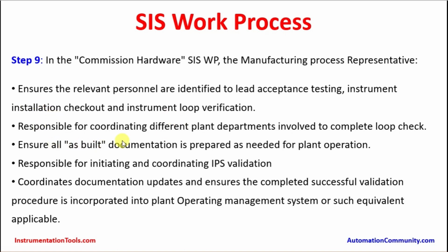He is responsible for coordinating different plant departments involved to complete the loop check. Loop check is one process wherein the instrument technician or electrical technician feeds a signal from the field, at the plant location, and sees that the respective readings are registered in the DCS and the HMI operating screens. Ensure all as-built documentation is prepared as needed for plant operation.